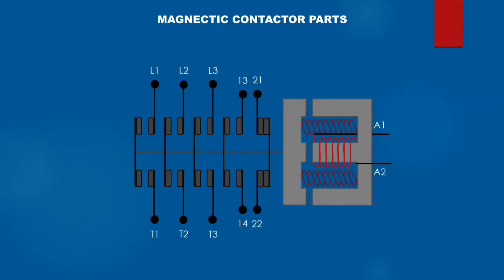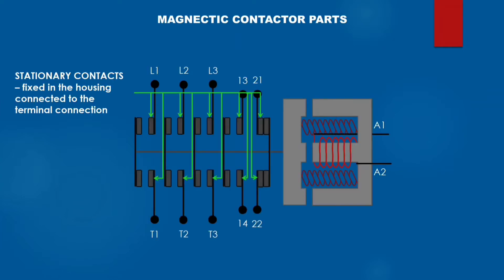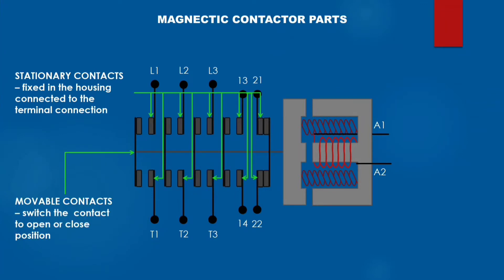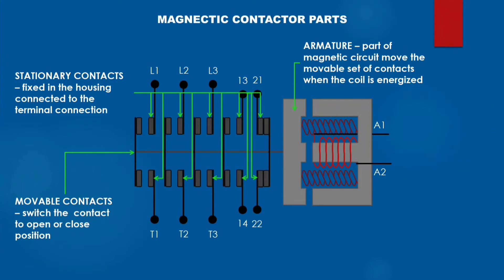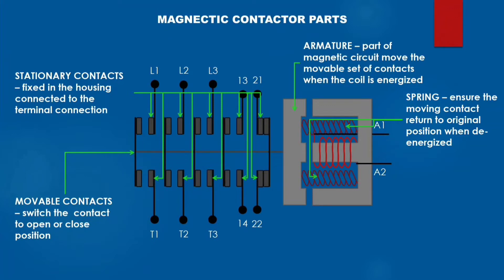Magnetic contactor parts: stationary contacts are fixed in the housing and connected to the terminal connection. Movable contacts switch the contact to open or closed position. The armature is part of the magnetic circuit that moves the movable set of contacts when the coil is energized. The spring ensures the moving contact returns to its original position when de-energized.